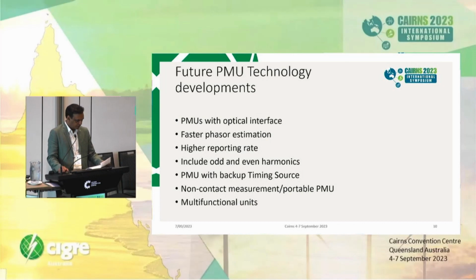Optical sensors convert light rays into electronic signals and convert them into a form that is readable by an instrument. Their output is highly accurate current and voltage, providing electrical isolation, linearity, and temperature stability, and having great potential for future applications. Compared with PMUs connected to conventional CTs and VTs, optical PMUs will be immune to electrical noise, with higher measurement accuracy, and more tolerant to solar magnetic disturbance and electromagnetic pulses.